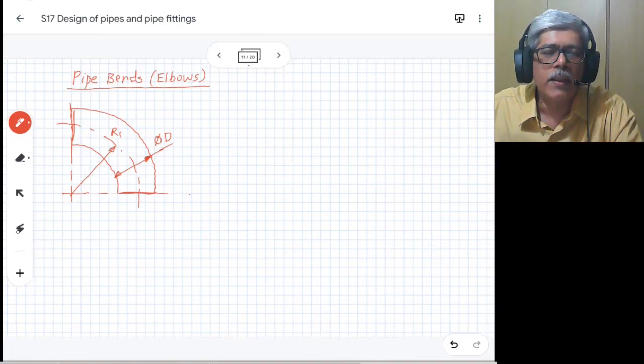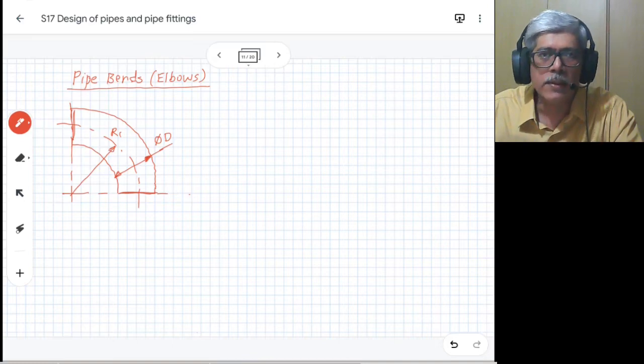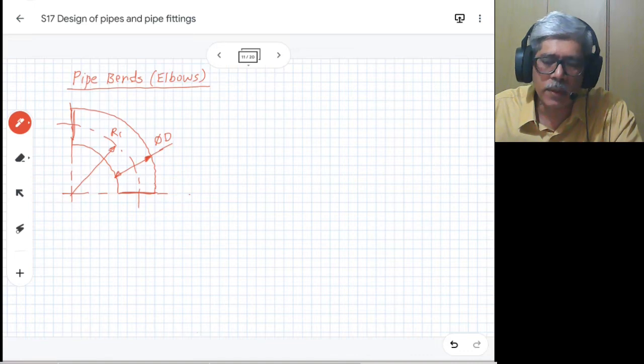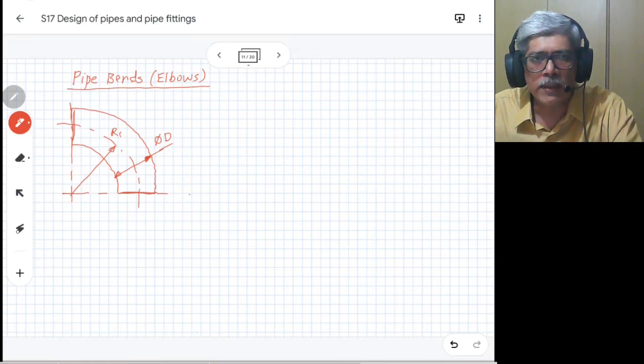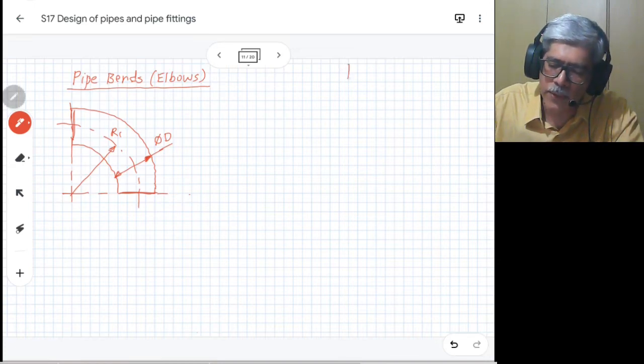Let's understand the thickness calculation for pipe bends. This is applicable to pipe bends which are formed - the pipe bends which have a clean bend radius. For them, this particular method can be used. There are other types of pipe bends which are known as miter pipes or miter bends.